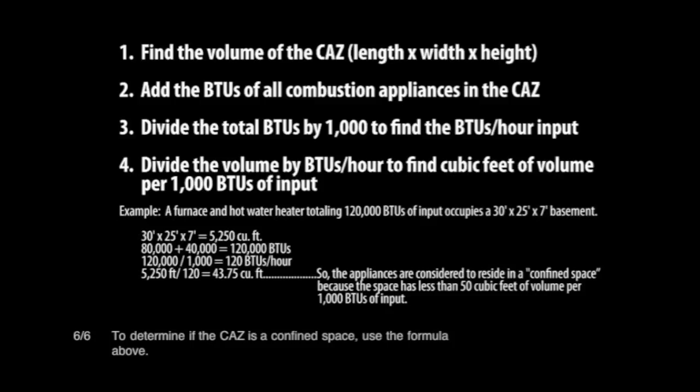For example, a furnace and hot water heater totaling 120,000 BTUs of input occupies a 30-foot by 25-foot by 7-foot basement. 30 × 25 × 7 equals 5,250 cubic feet. 80,000 plus 40,000 equals 120,000 BTUs. 120,000 divided by 1,000 equals 120 BTUs per hour. 5,250 divided by 120 equals 43.75 cubic feet. In this case, the appliances are considered to reside in a confined space, because the space does not have 50 cubic feet of volume per 1,000 BTUs of input.